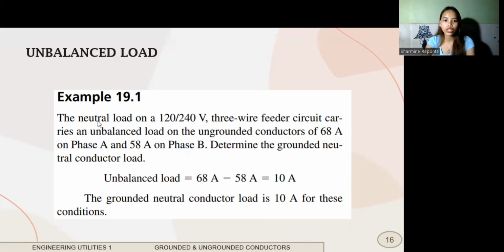Example 19.1: The neutral load on a 120/240 volt 3-wire feeder circuit carries an unbalanced load on the ungrounded conductors of 68 ampere on phase A and 58 ampere on phase B. Determine the grounded neutral conductor load. So to get the unbalanced load, we simply have to minus phase A to phase B. So 68 ampere minus 58 ampere is equals to 10 ampere. So atong unbalanced load diri is 10 ampere. 10 ampere nga ginadala sa atong neutral conductors.